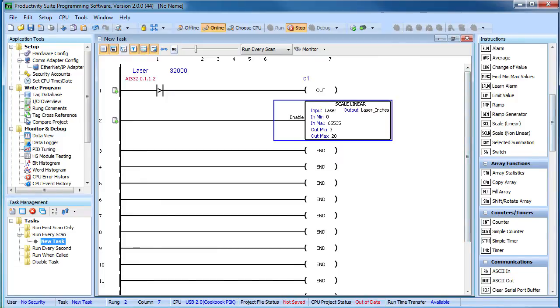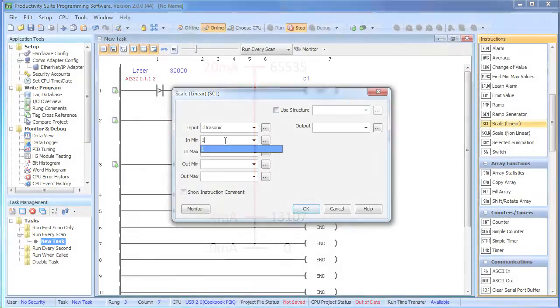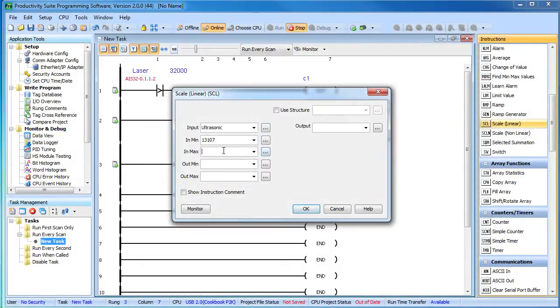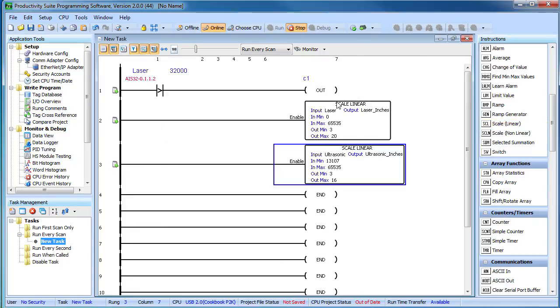The ultrasonic is a little bit different. The module's input range was 0 to 20 milliamps, which corresponds to the 0 to 65535 counts, but our sensor is 4 to 20 milliamps. So if we do a little math, we find that the input minimum is 13107, which goes here. The sensor was set up so that 3 inches is 4 milliamps and 16 inches is 20 milliamps, so we put that here. And we'll call that ultrasonic inches.